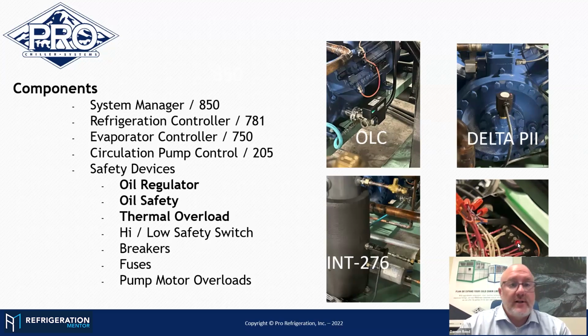And then inside of the compressor electrical box, we have the SEB5 thermal overload. So it's monitoring the thermal temperature on the compressor motor windings. If the windings get warm for whatever reason, that's going to open, trip, and you do get a red indicator light on the front of the compressor electrical box that we install. You push that button down, hold it for 3 seconds, it drops power. You let go, it'll reset if the thermal condition is no longer present. And this stuff is key.